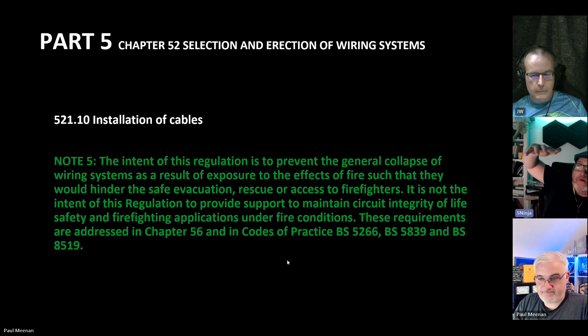John? Yeah, chapter 52, this is 526.9 - protection of multi-wire, fine wire, and very fine wire conductors, which already exist. Essentially what I've got now is a little table giving you some of the conductor classes 1, 2, 5, and 6, which are basically solid, stranded, fine, and very fine wires. There's a note that conductor classes refer to the different conductor constructions as defined in BS EN 60228. That's existed forever - they've just put a tiny bit of it into BS 7671.